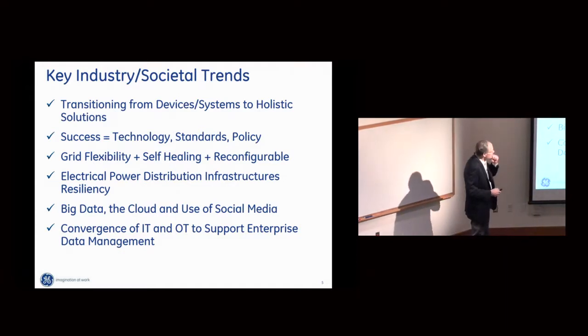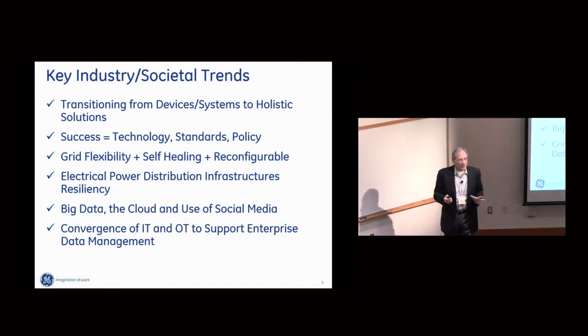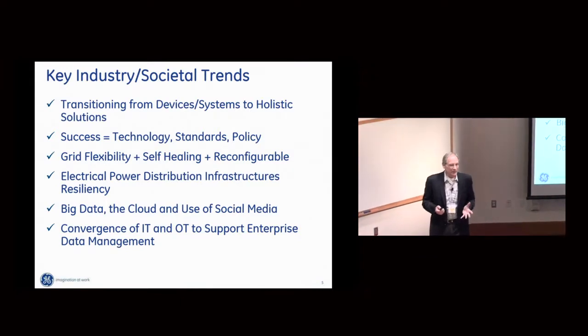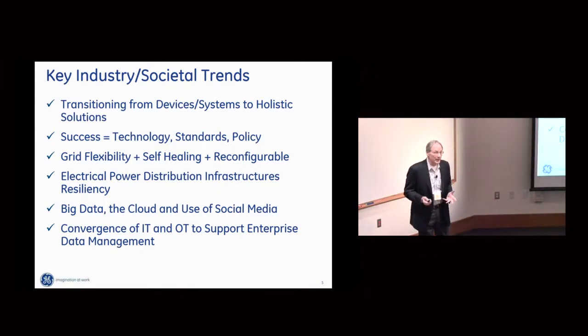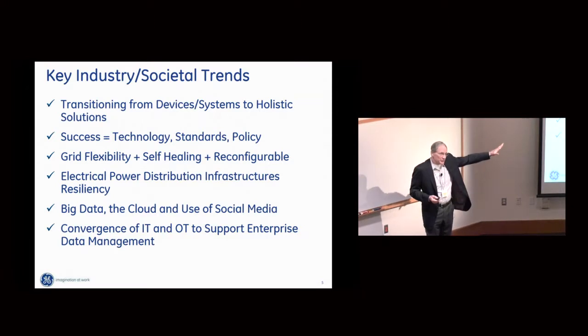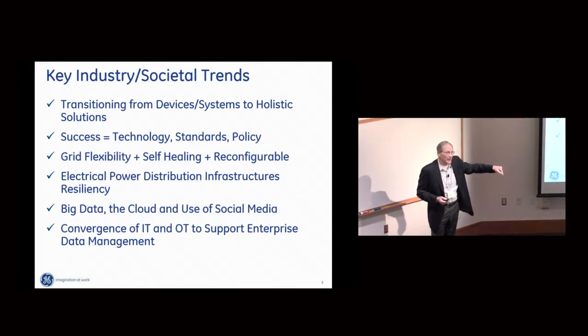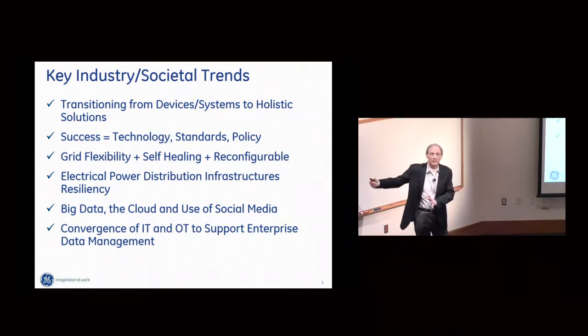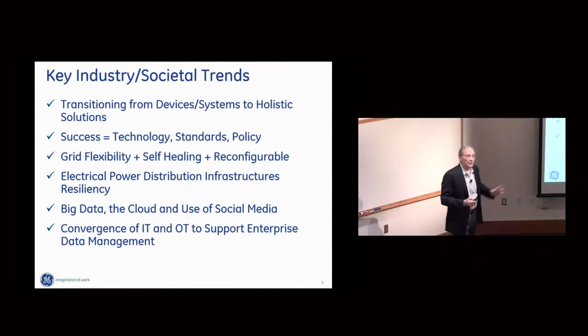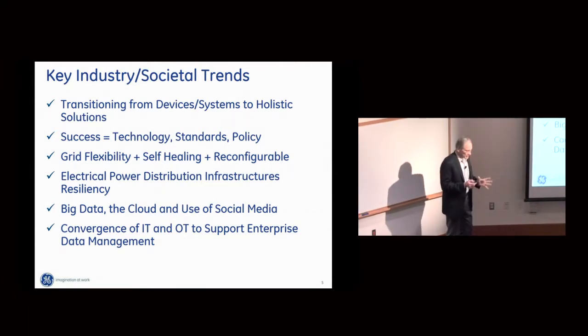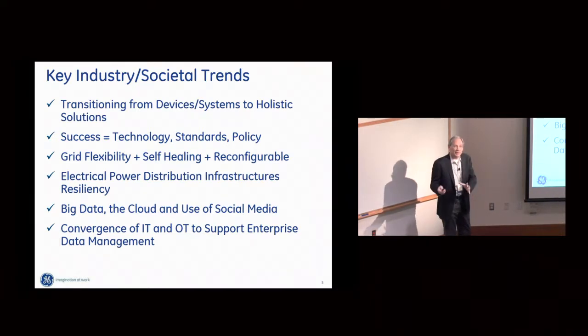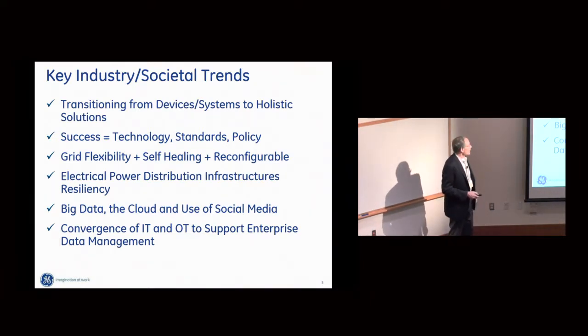A dispatcher just can't react fast enough in an emergency situation in less than 5 minutes, so let's work more on self-healing. Once we have confidence in the logic, let's close the loop on it. With generation and transmission, we've closed the loop on automatic generation control logic in an EMS for decades — we let an EMS send 100 or 200 millisecond pulses to a power plant and move large generators with no human in the loop every 4 seconds. So it's about distributing the intelligence and having confidence in the logic to close the loop.